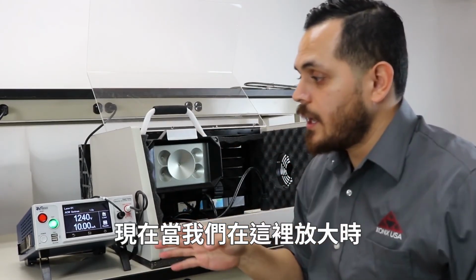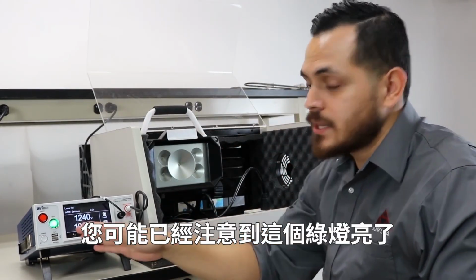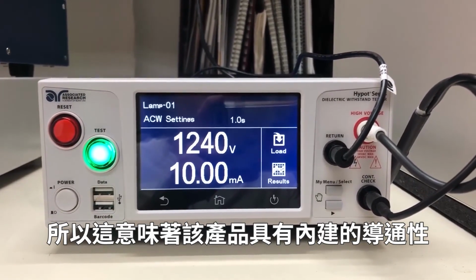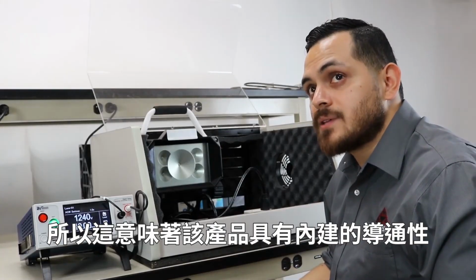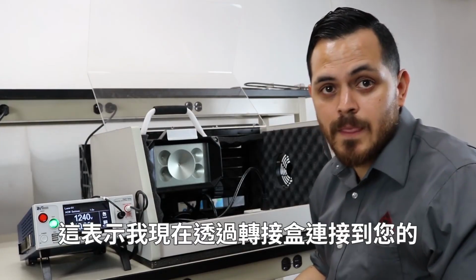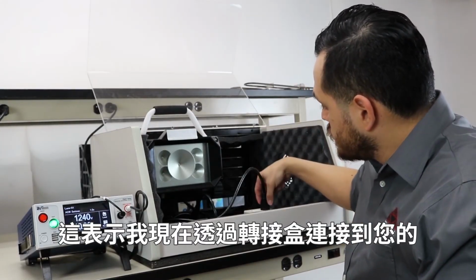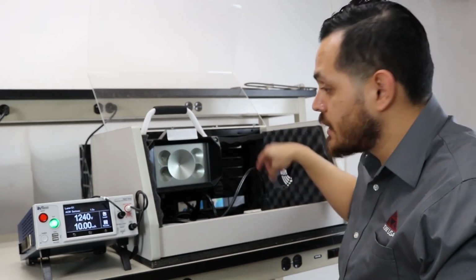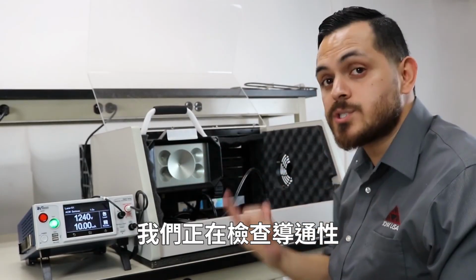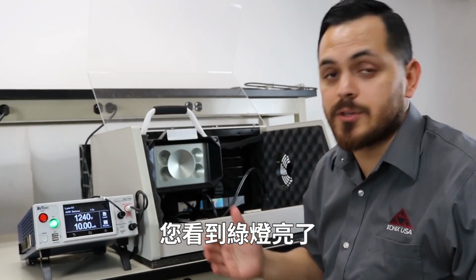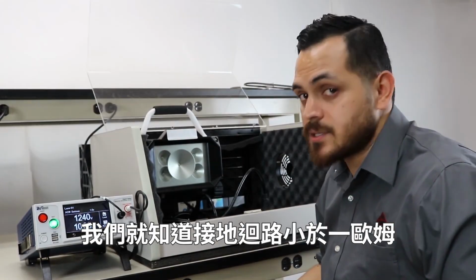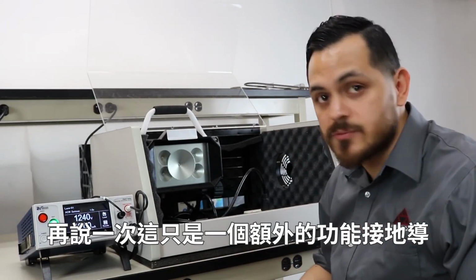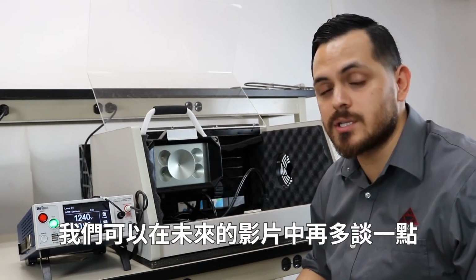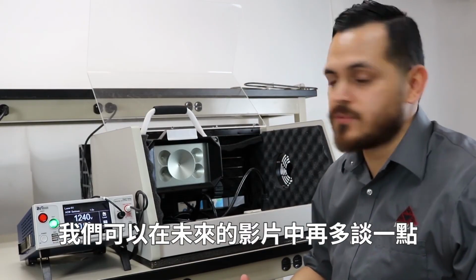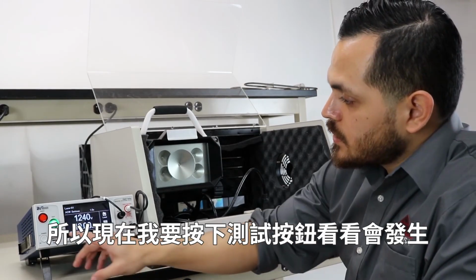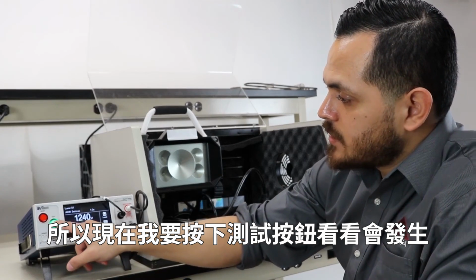Now, as we zoom in here, you may have noticed this green light turned on. So what that means is the product has a built-in continuity test, meaning I've now access to your ground through the adapter box, and I've just returned the alligator clip. We're checking for continuity. We see the green light. We know that the ground circuit has less than 1 ohm. Again, that's just an extra feature, ground continuity. We can touch on that a little bit more in future videos. So now I'm going to hit the test button and we'll see what happens.